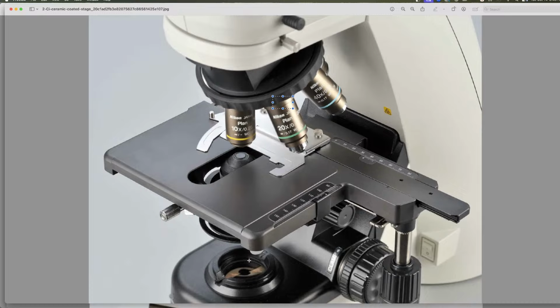And once you have the illumination plane done like that, you can center the condenser with these two screws. One of them makes it move a bit to the left, one of them makes it move a bit to the right. Obviously, that's why the screws are on either side. And you can position the condenser absolutely in the dead center of your field.